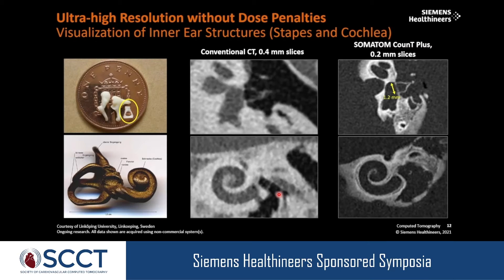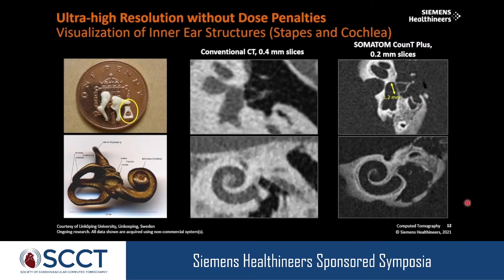The capabilities are shown in comparison to conventional CT. Images of the stapes — the smallest bone in our body — show that at 0.4 mm slice thickness, the structure is barely visible with conventional CT, but substantially better visualized with photon counting CT. The distance between the two legs is just 1.2 mm. Similarly, the cochlea shows dramatically better visualization compared to conventional CT. For coronary stents, the resolution improvement is also substantially higher.